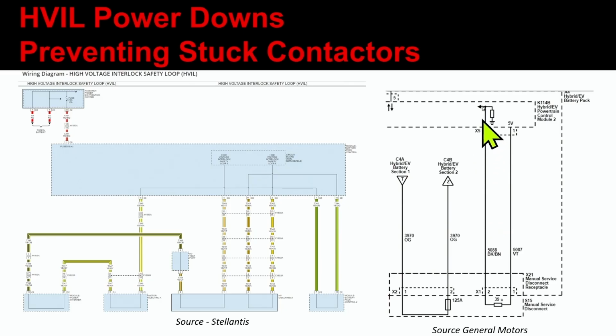So we have a certain voltage, not necessarily zero, that tells that computer, yep, not only do I see high voltage connected across the big fuse from the battery pack sections, battery section 1 and 2, that still could be a 2 mode, but also I have closed the final part, the HVIL section of that service disconnect.